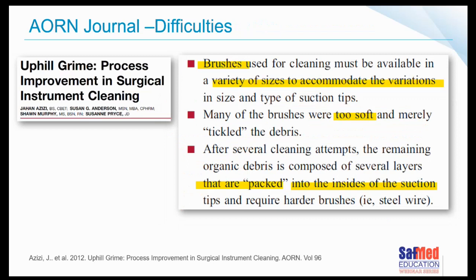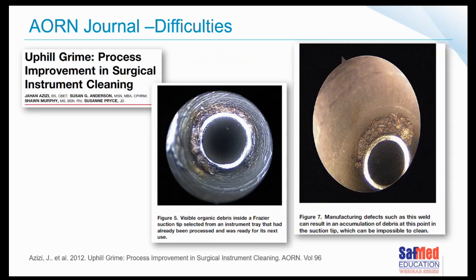So here were some of the points that they found. The brushes they were using for manual cleaning needed all sorts of sizes, and they didn't have all of the right sizes. And remember, how do you get inside the bulge of that Yankauer sucker? I have no idea. They found some brushes were too soft and just tickled at the debris and didn't do the job. They also found several layers of debris packed on the inside over time, and in fact couldn't get it out at the end of the day.